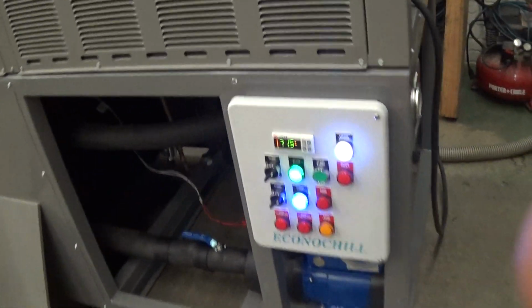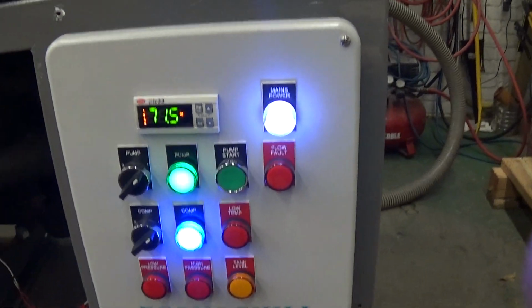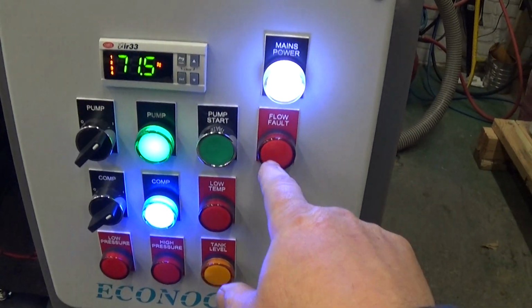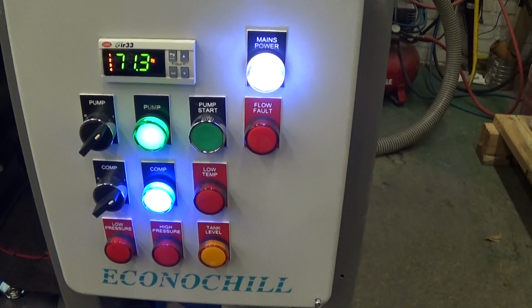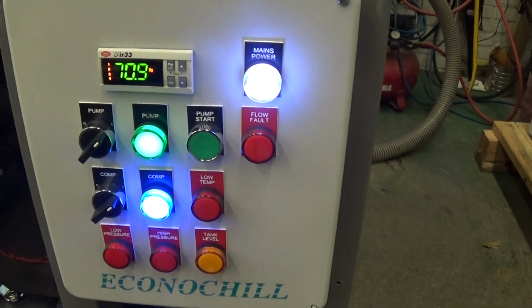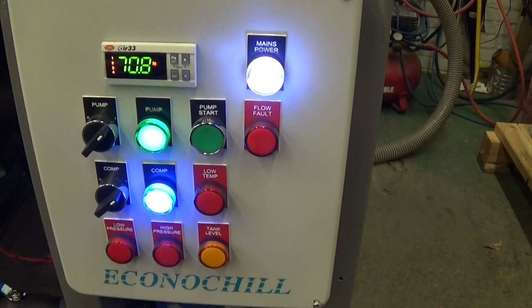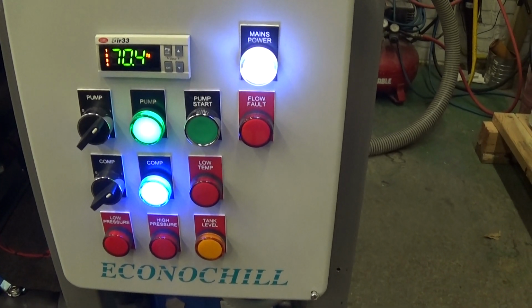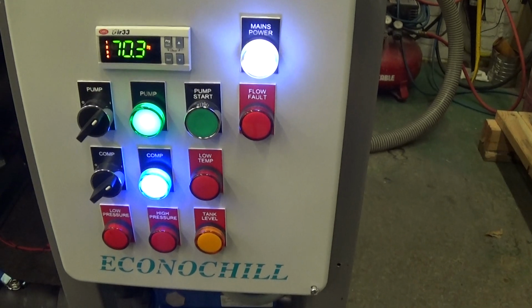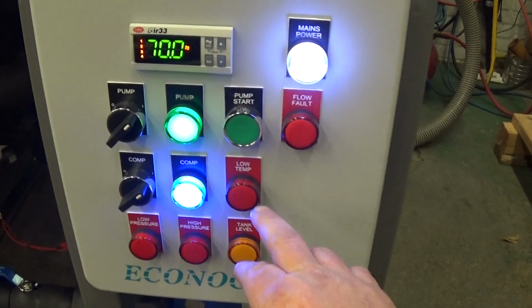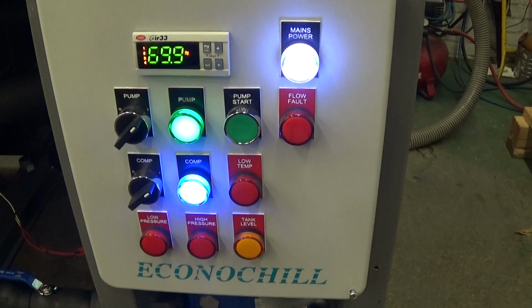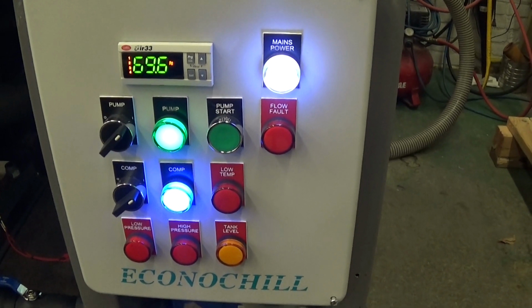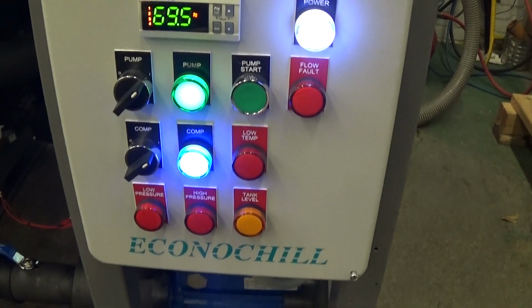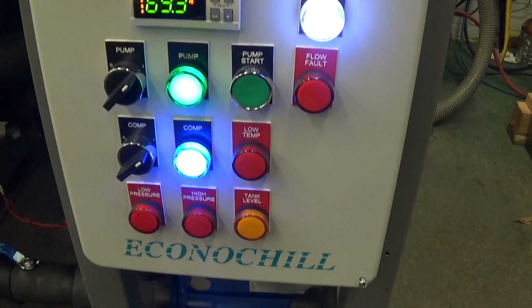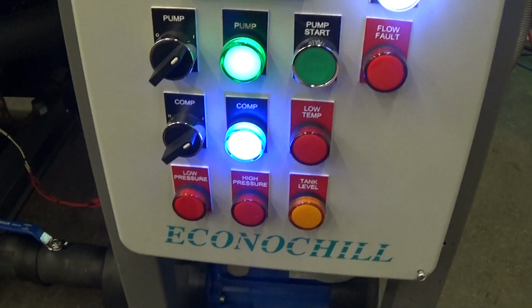So a couple more things about the controller. Flow fault, that will happen if the flow switch is not satisfied. That's a common startup adjustment. Again, the flow fault is there to make sure you have enough flow going to the heat exchanger, the chiller. Low temp, that's what will come on if the freeze stat that I mentioned earlier is triggered. Low pressure relates to refrigerant low pressure. High pressure is refrigerant high pressure alarm.